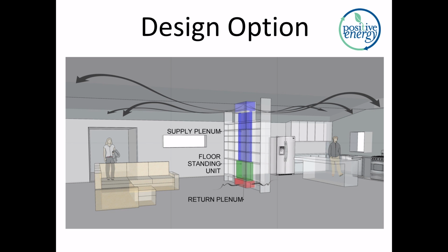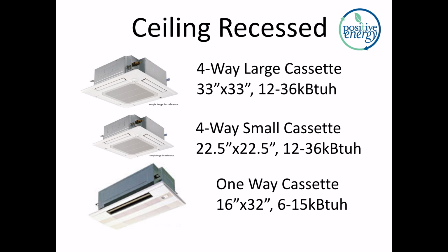Okay, so the next of the 3 broad categories are ceiling recessed. Again, this is representative of a class of products. There's typically small and large 4-way cassettes, and then there are 1-way cassettes. The main difference between the small and large 4-way is that on the larger ones, all the service can be done through the faceplate, whereas on the smaller ones, typically you need to provide a separate auxiliary service access port off to the side. The 4-ways can have up to 2 of the 4 directions shut down and then ducted to an auxiliary space. This could be fantastic for a master bedroom with the cassette, and then you put the auxiliary duct to the master bath. These units can receive ventilation air. The 1-way cassettes, I know of whole homes that have been designed to have these 1-way cassettes in them. 1/2 ton to 1.25 tons on there.